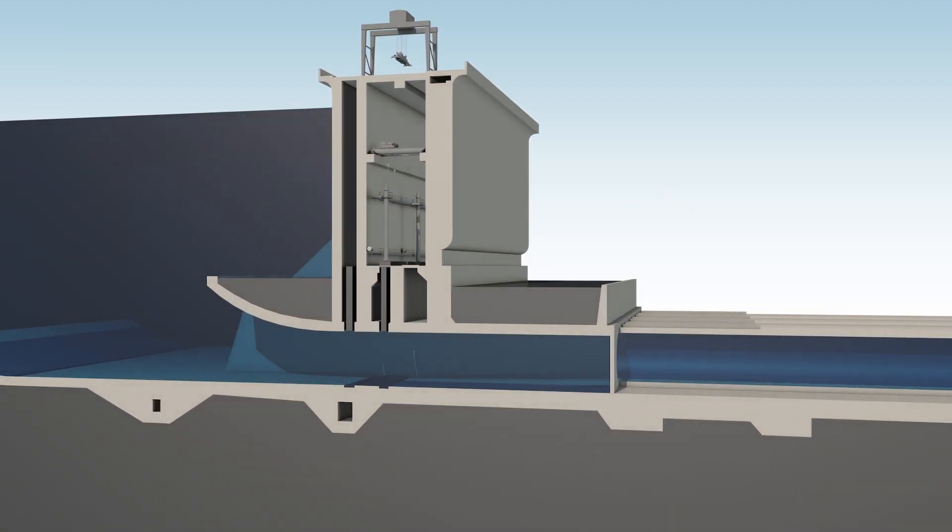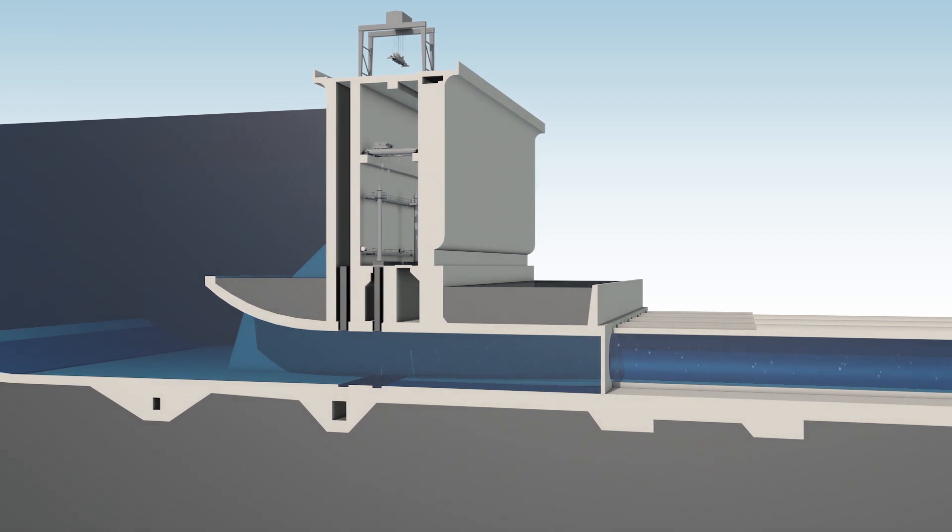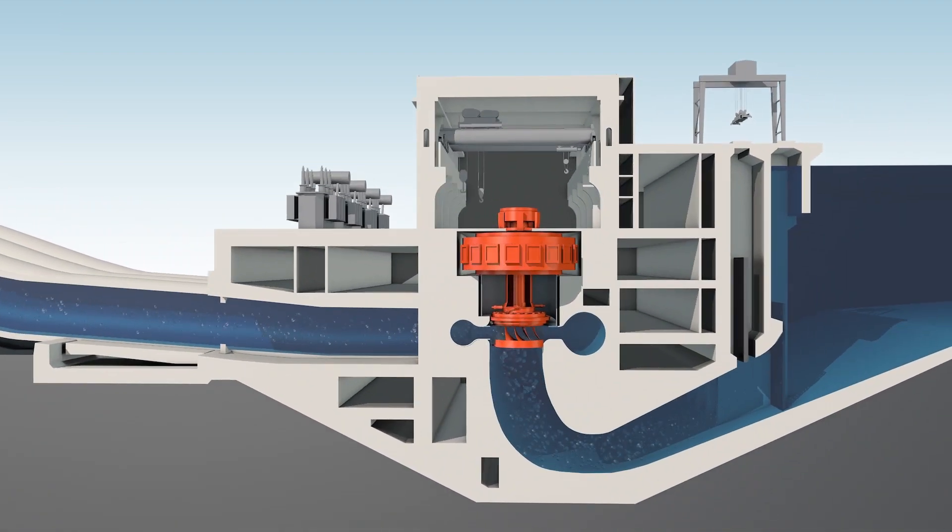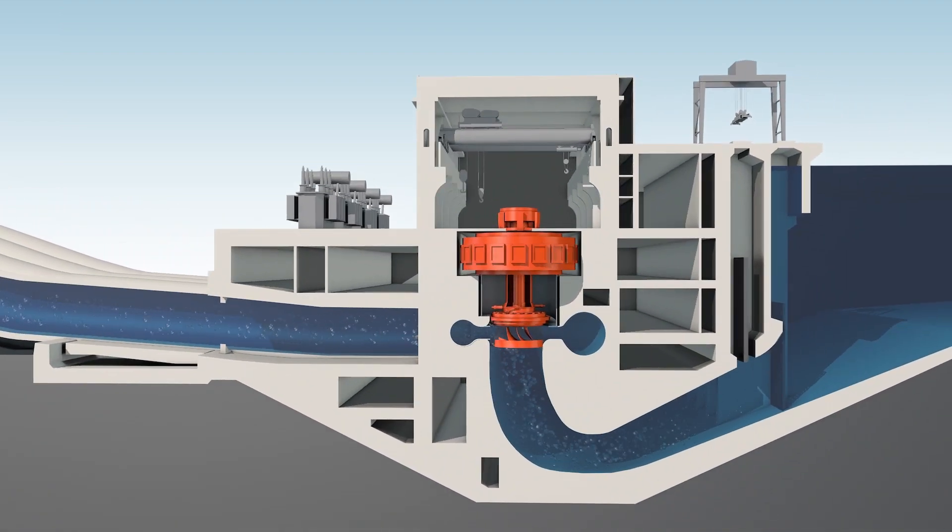During the daytime, when electricity demand is higher, the direction is switched and water from the upper reservoir is released back down through the penstocks into the turbines, making them spin. The turbine runners rotate around the same shaft, but now in the opposite direction, thus driving the generators in order to produce electricity.